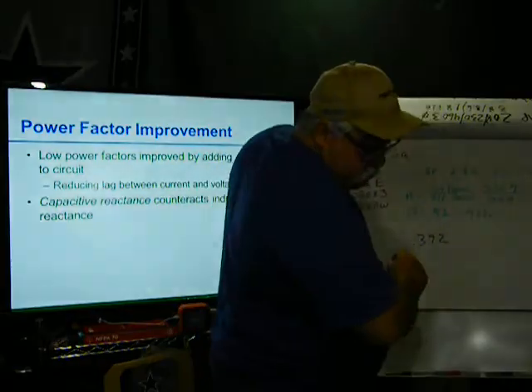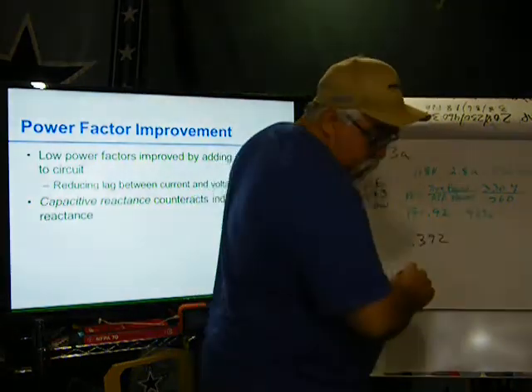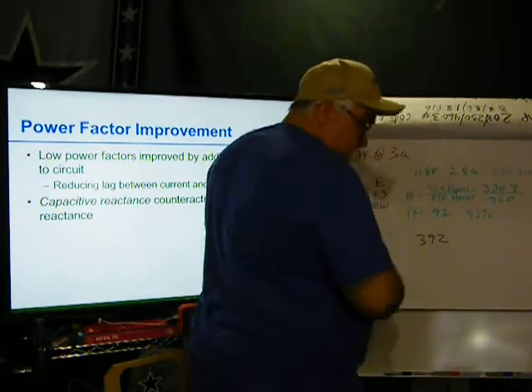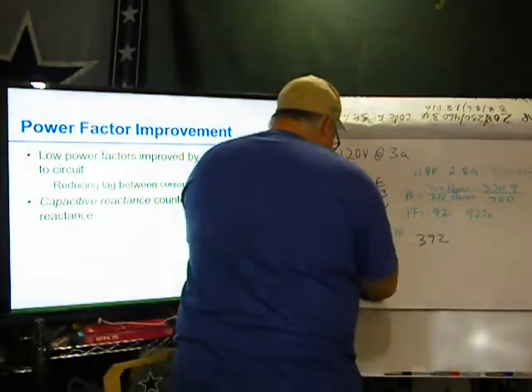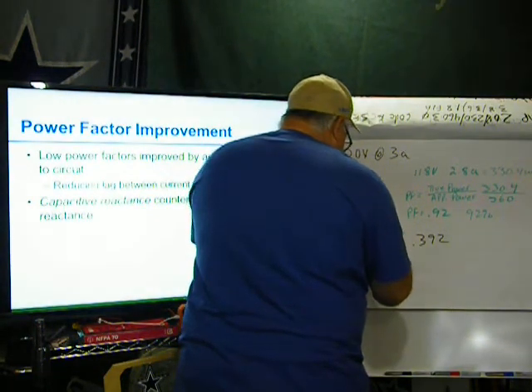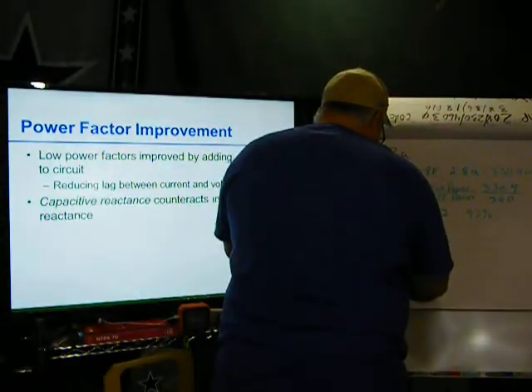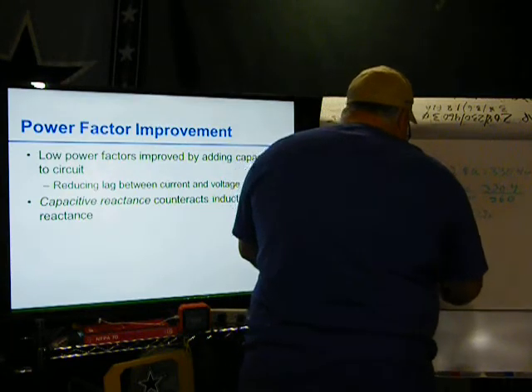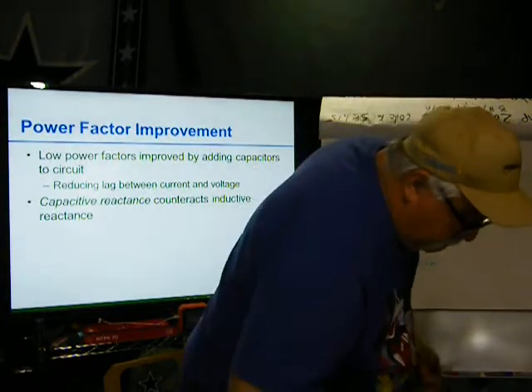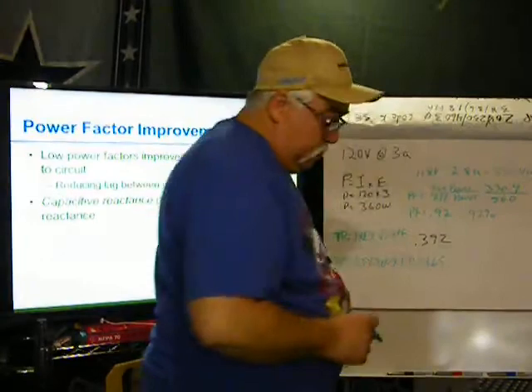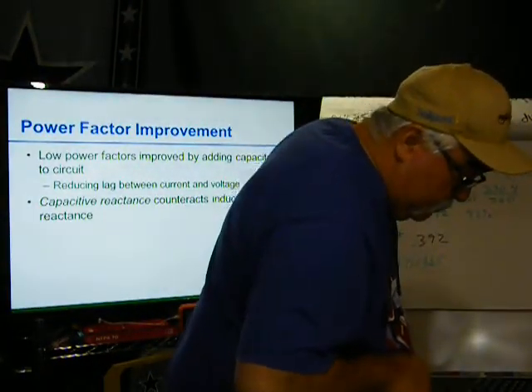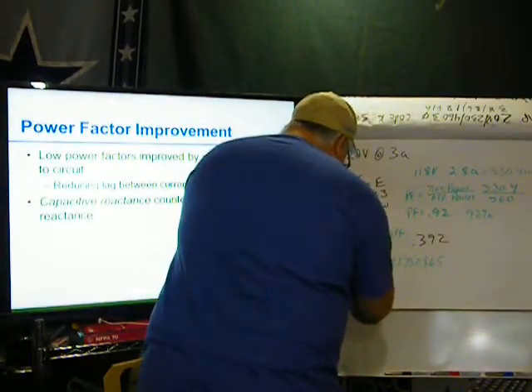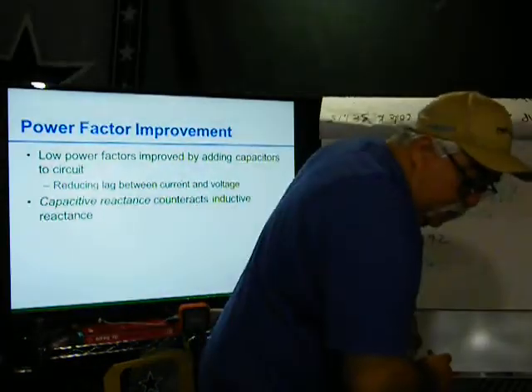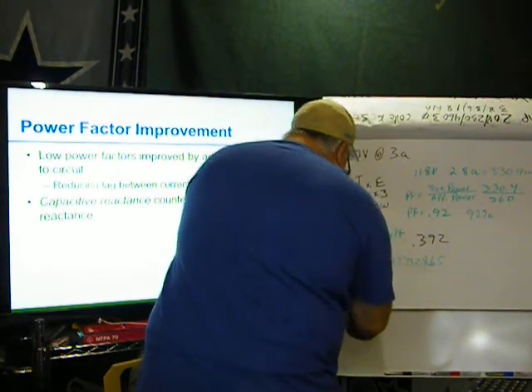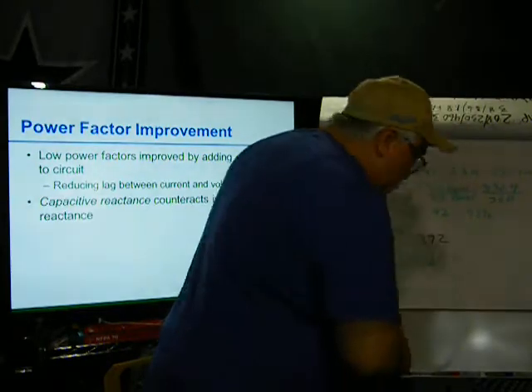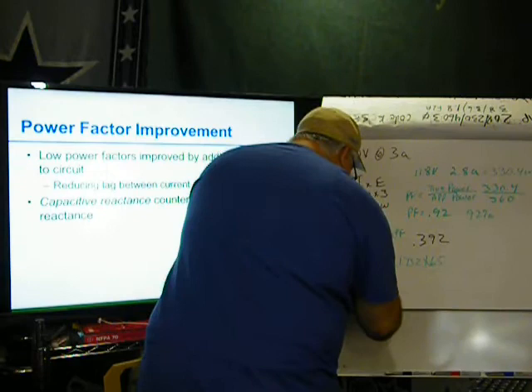True power equals I times E times the square root of 3 times power factor. So true power equals 65 amps times 460 volts times 1.732 times 0.65. That's 65%, 0.65. So true power equals 33,661, or 33.6, 33.7 kW.